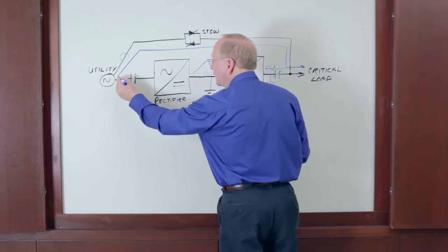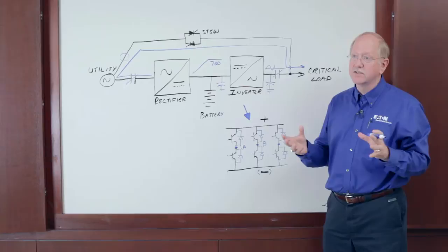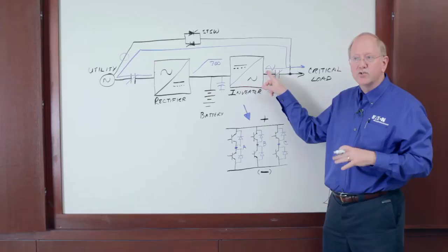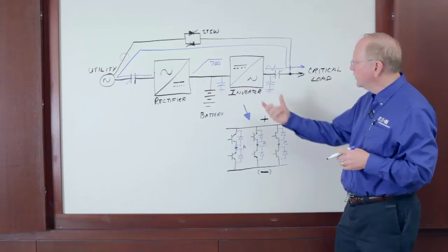So with closed contactors, I have voltage here and I have voltage here. The rectifier and inverter are suspended, but the inverter is still generating its gate commands for its main power transistors. It's not actually firing those transistors, so it's not using any power. But the gate command signals are already in sync with the output here, so I don't have to wait for sync when I flash the inverter on.